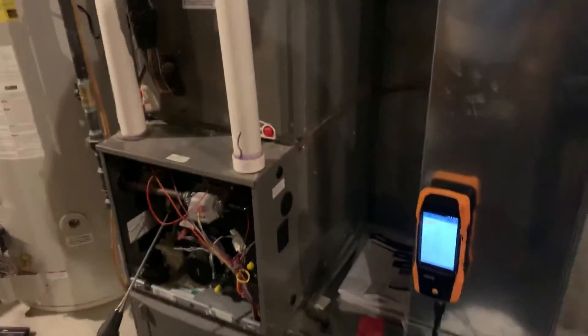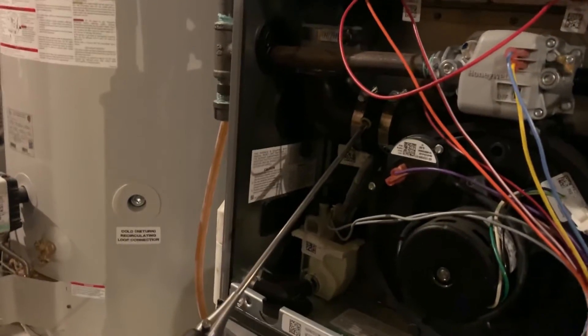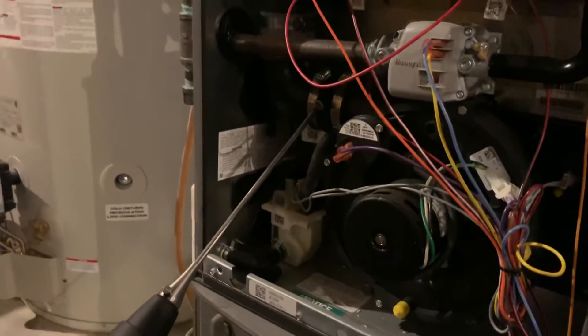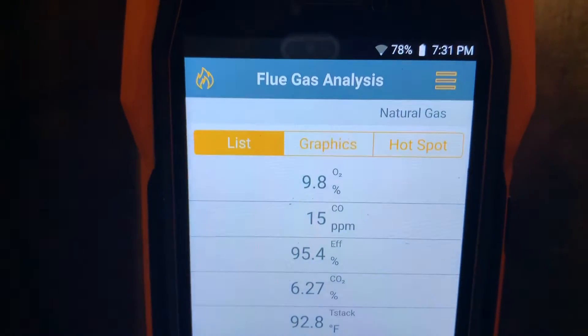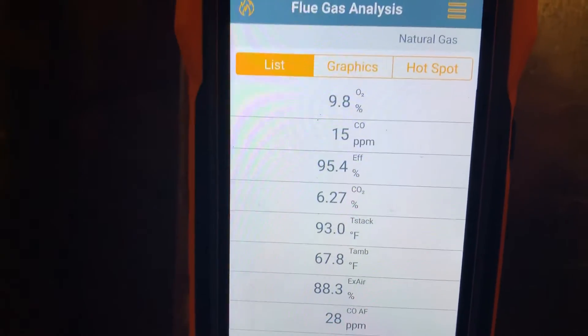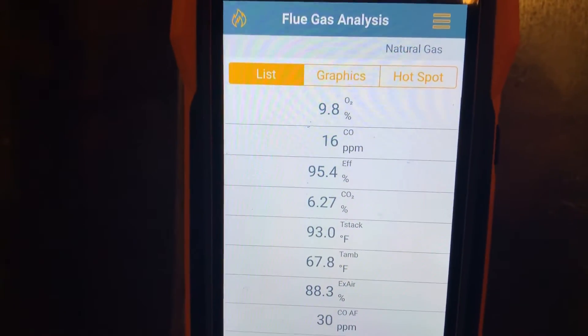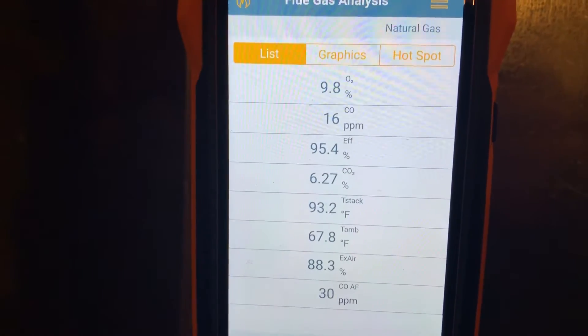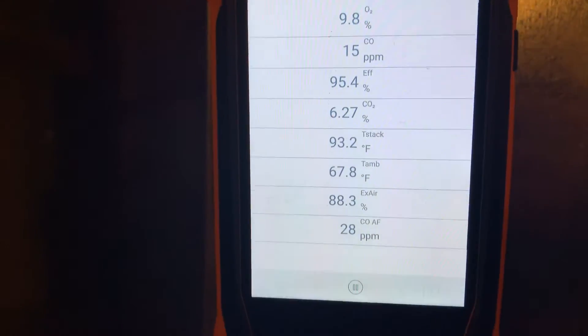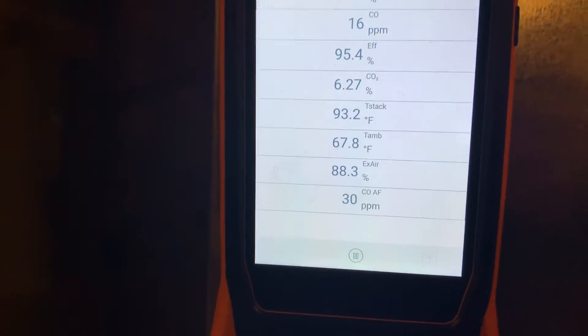This is their brand new product — it's been out for about a month and a half to two months. Right now I've got my test probe in the outlet side of the draft inducer assembly. Here are my numbers: I've got 9.8% on oxygen, 15 parts per million of carbon monoxide, efficiency of 95.4% — which is dead-on — CO2 is at 6.27%, and my stack temperature T-stack is at 93.2.